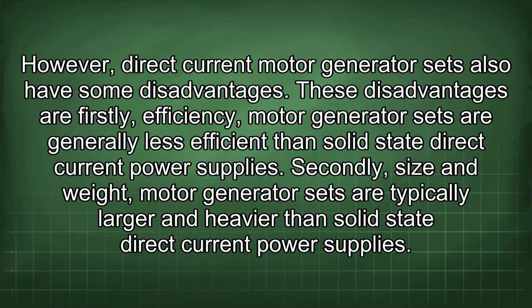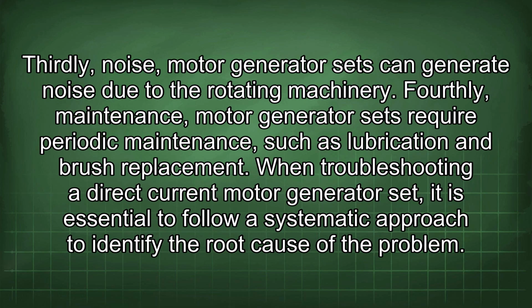However, direct current motor generator sets also have some disadvantages. These disadvantages are firstly, efficiency. Motor generator sets are generally less efficient than solid-state direct current power supplies. Secondly, size and weight. Motor generator sets are typically larger and heavier than solid-state direct current power supplies. Thirdly, noise. Motor generator sets can generate noise due to the rotating machinery. Fourthly, maintenance. Motor generator sets require periodic maintenance, such as lubrication and brush replacement.